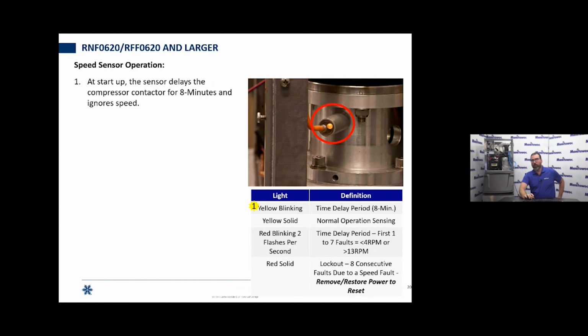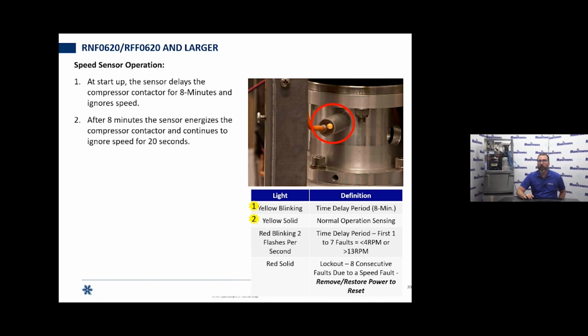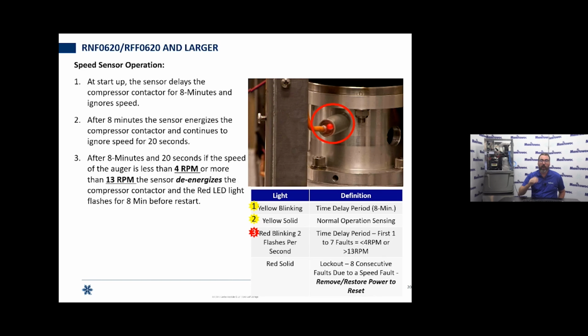So I talked a little bit about this already, but of course at startup, our sensor time delay is going to be active. We're going to have that yellow flashing light. That's an 8-minute time period where it doesn't care what's going on. It's basically just letting that machine get up to running condition, kind of normalized, just give it that time to equalize everything out. Now, after 8 minutes and 20 seconds, there's a brief period of 20 seconds just to make sure everything's working. We should see that yellow light go solid. At that point, we should be running. Our compressor motor should have started and we should be making ice.